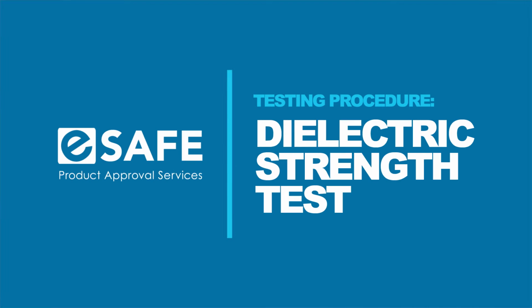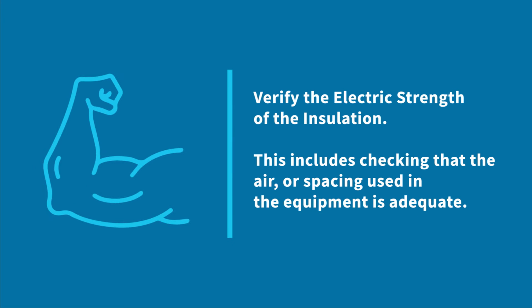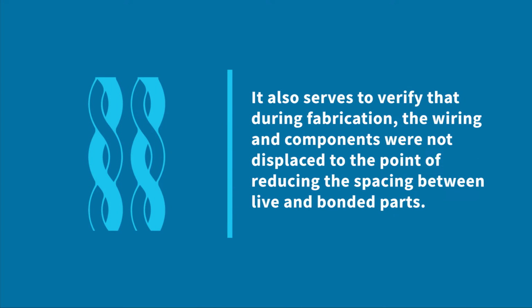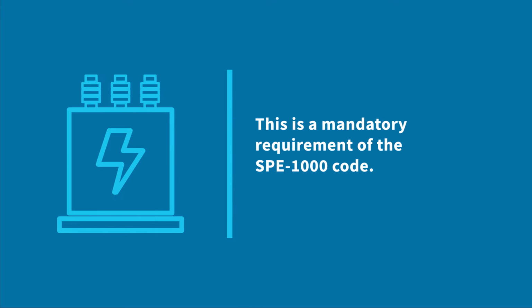Testing procedure. Dielectric strength test. The purpose of the dielectric strength test is to verify the electric strength of the insulation. This includes checking that the air or spacing used in the equipment is adequate. It also serves to verify that during the fabrication, the wiring and components were not displaced to the point of reducing the spacing between live and bonded parts. This is a mandatory requirement of the SPE 1000 code.